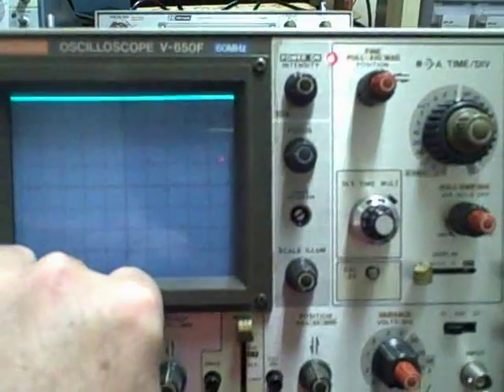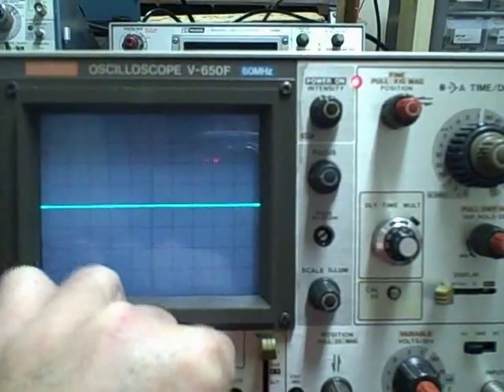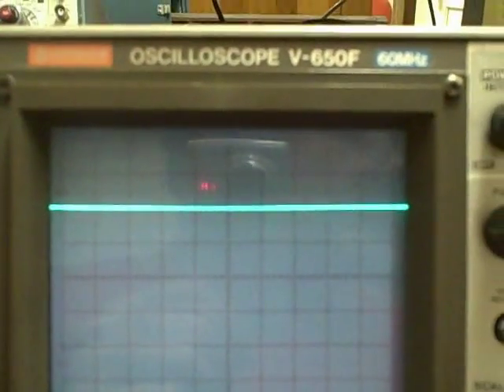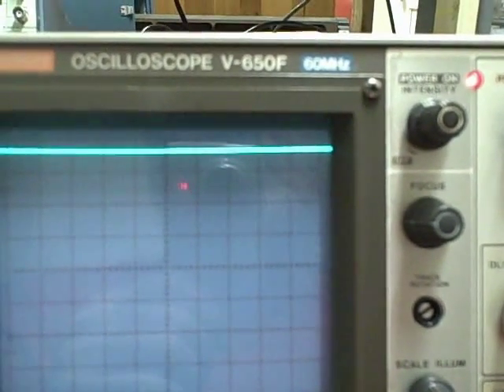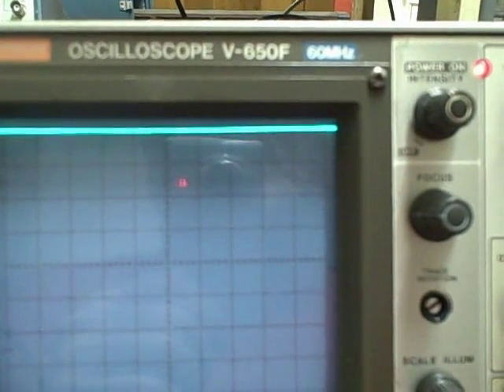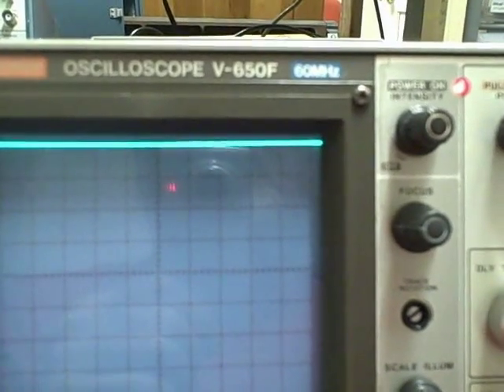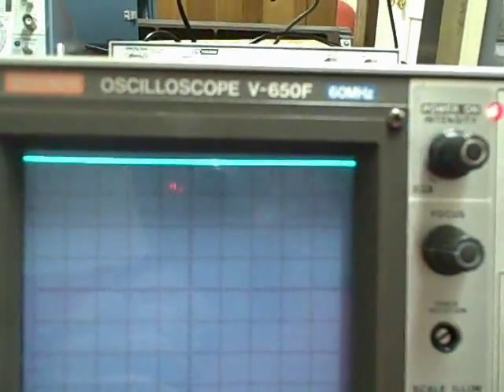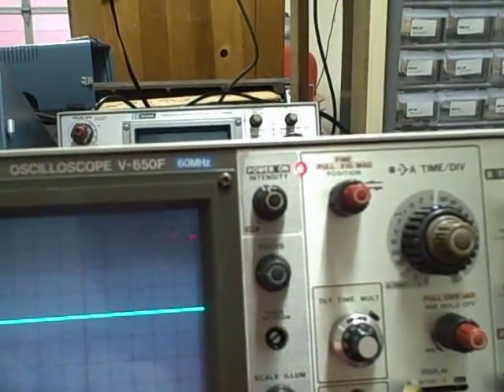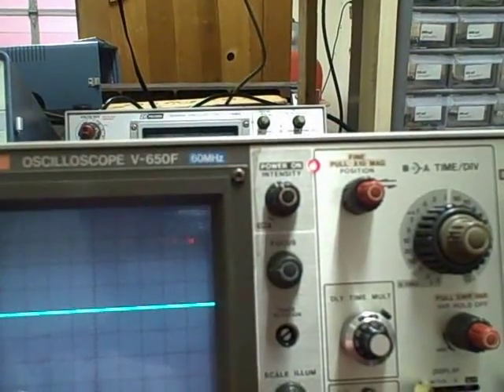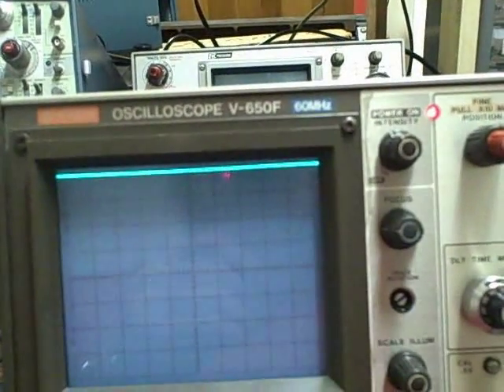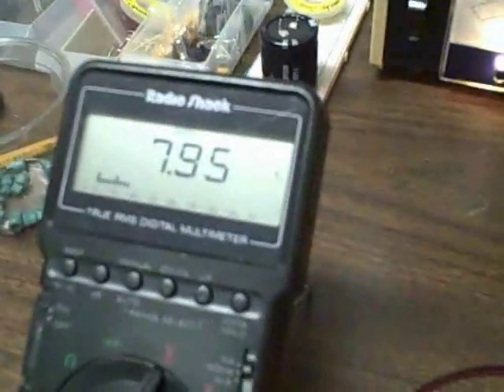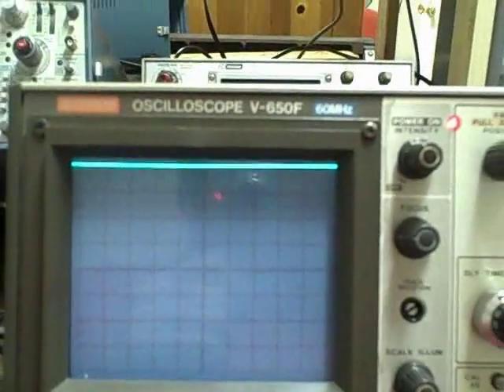Let's go ahead and put her on two volts per division. And we are two divisions up, so that's four volts, which is correct. Let's go ahead and kick ourselves up full scale. Full scale would be right about there. Check our zero once again here. Zero is right there. And full scale is right there. We are running 7.95. Within five hundredths of a volt, we're displaying eight volts. Two volts per division, four divisions, eight volts.